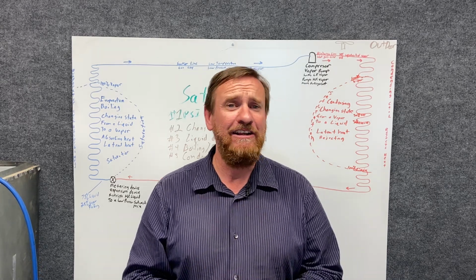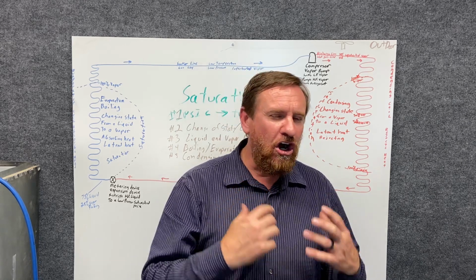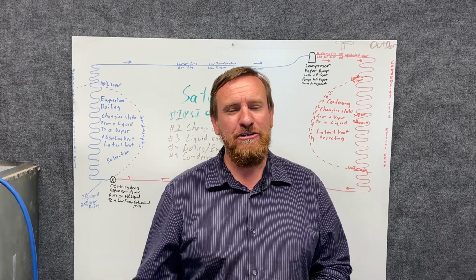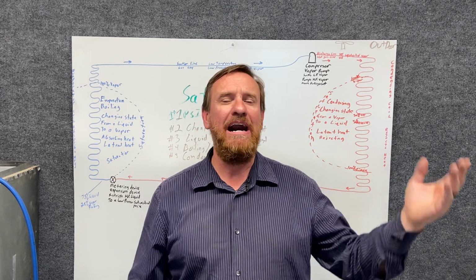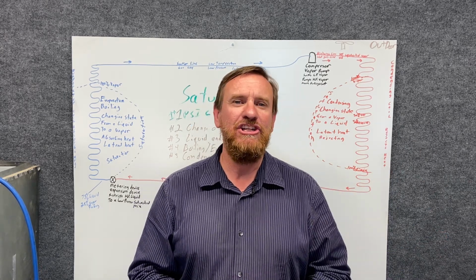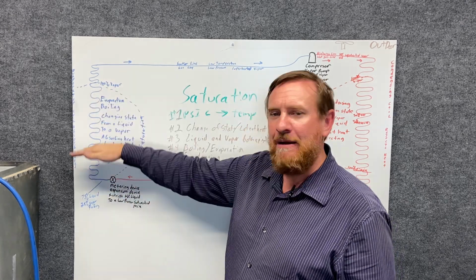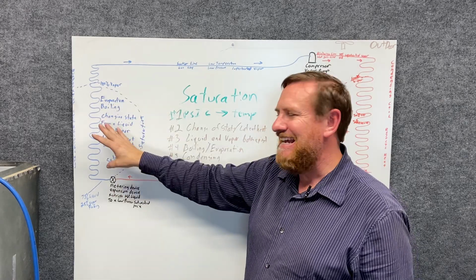We're going to talk more about this later. It's a very important concept. It's also a type of saturation. Once all of the ice melts, then the temperature can either drop lower or go higher. But as long as there's ice and liquid together, it cannot change in temperature. It has to all change. So evaporation, whatever evaporator coil temperature is, it's going to stay that temperature.